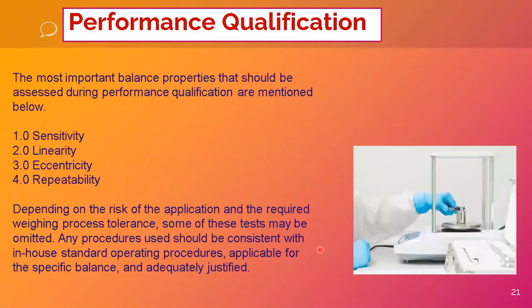Now, performance qualification: the most important balance properties to assess during performance qualification are sensitivity, linearity, eccentricity, and repeatability. Depending on the risks of the application and the required weighing process tolerance, some of these tests may be omitted, but any in-house procedure used should be consistent with the standard operating procedure applicable for that specific balance and adequately justified. In-house tests must at least fulfill the purpose of all four listed tests.